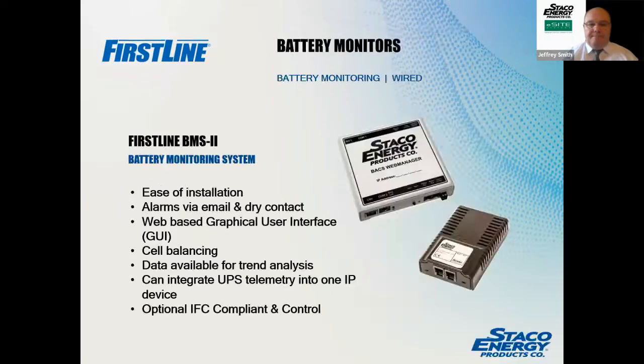Battery monitoring systems. We put in battery monitoring as required by the specifications, mainly for the individual batteries, so we can monitor each one. If you do it right and trend the batteries, you can actually see when they're going to go bad. The weakest link of any UPS system, no matter the manufacturer, is the batteries. So if you monitor and trend them, you can remove batteries before they actually fail. If you do that right, you end up with a better system overall.